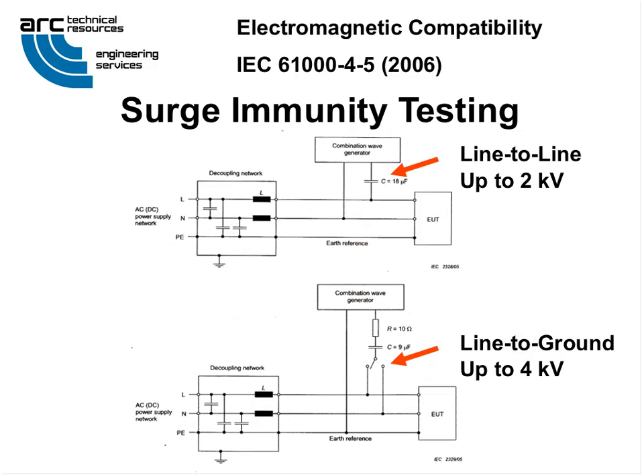2 kV, 1 kV line to line, 2 kV line to ground, or twice that for inside the substation fence on AC power lines. 5 positive and 5 negative hits are delivered each at 0, 90, 180, and 270 degrees at 1-minute intervals. That's 40 hits per voltage level, and all lower levels must be satisfied first. Wait your 1 minute in between or the product's going to get hot and fail.